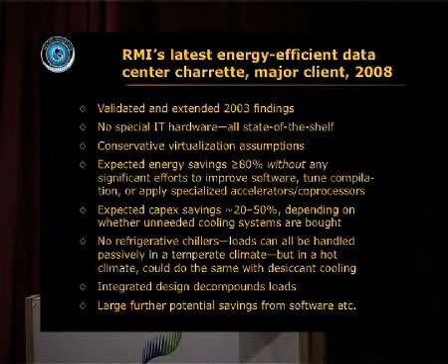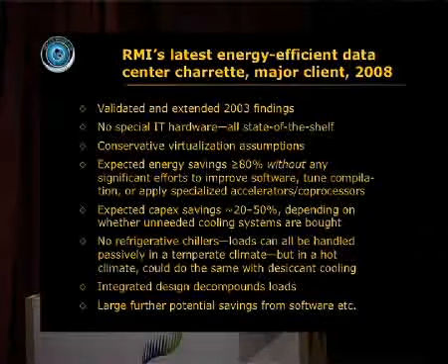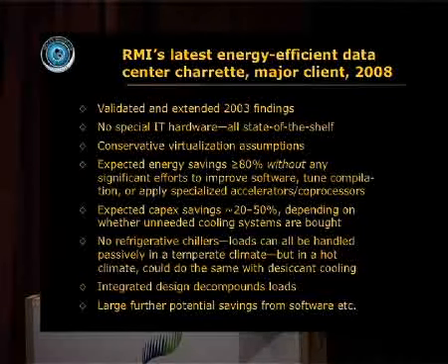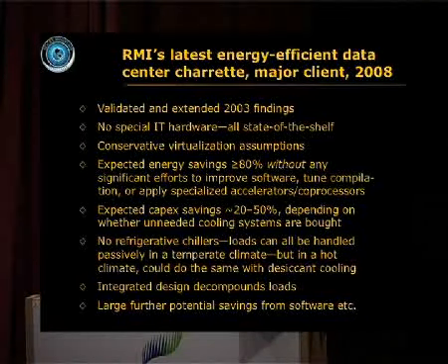But the loads in the temperate climate, this is not in Singapore, could all be handled passively according to standard mechanical practice. However, in a hot climate, you can do the same thing with desiccant cooling, as I'll describe. So you still wouldn't need refrigerative chillers. And there was a highly integrative design and a lot still to be done on the software side to push the savings to and above 90%.